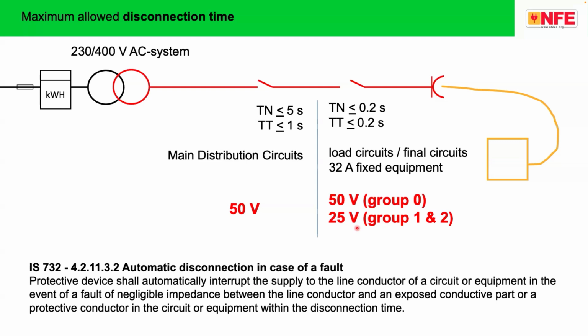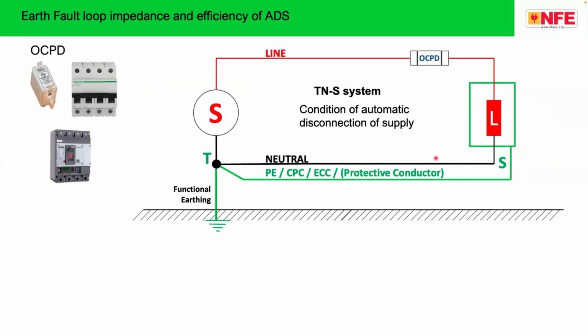As I said, one of the most important safety measures is called efficiency of automatic disconnection of supply. There must be a protective device. As you can see here, this is a protective device. This protective device must trip within the time in case of a fault on the circuit, fault on the conductor, or fault on the equipment. The device must trip. How does this trip?